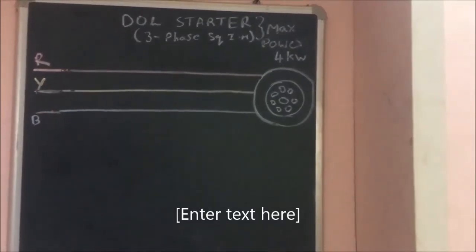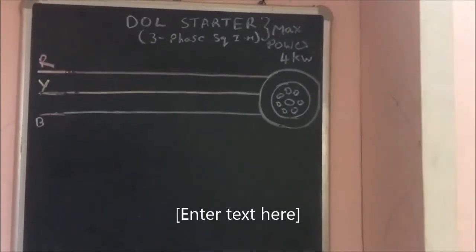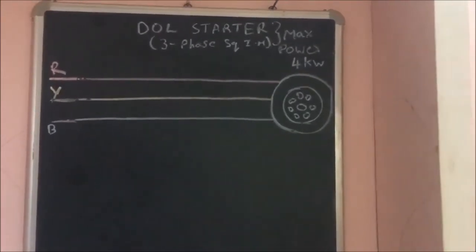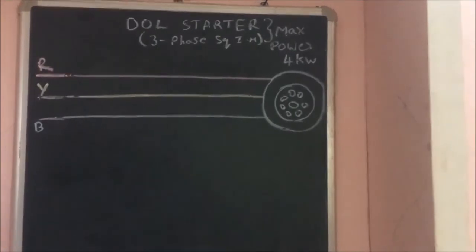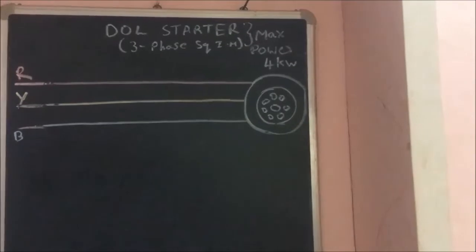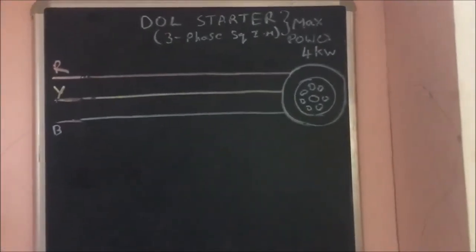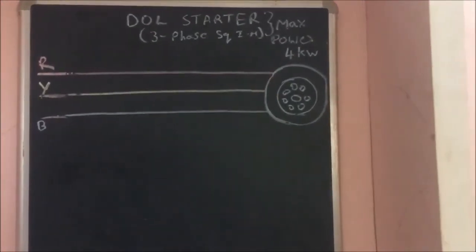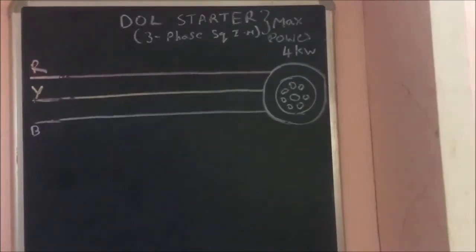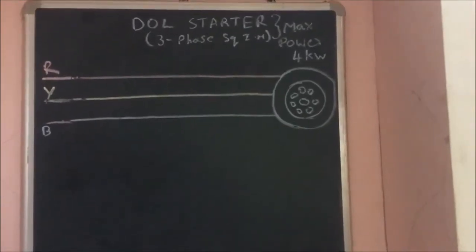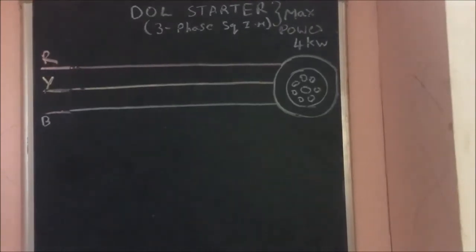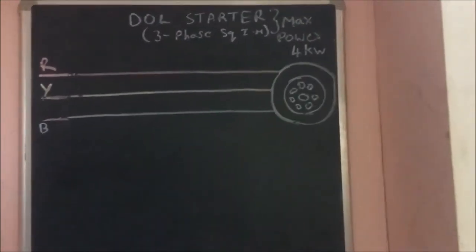In this class we are going to see about the direct online starter, by drawing as well as understanding the concept. Normally the direct online starter is used for three-phase squirrel cage induction motors of low power rating up to 4 kilowatt. Because at starting time the back EMF is zero, therefore the starting current is 2 to 5 times the rated current, and therefore heat loss I²R will be more, and power losses also increase.